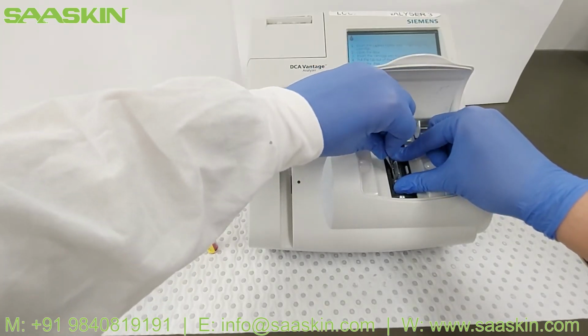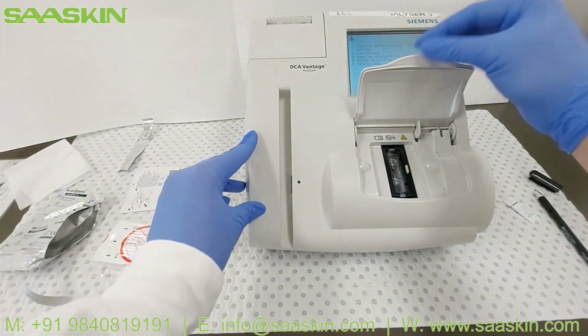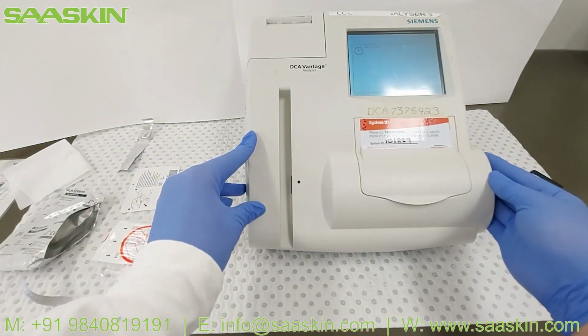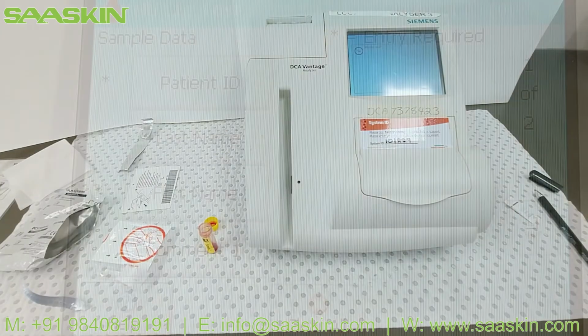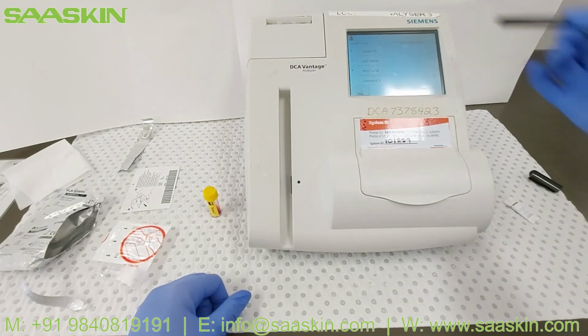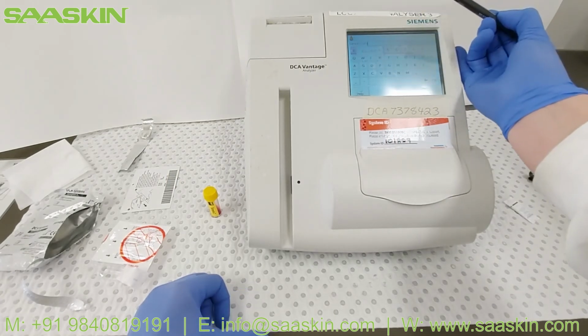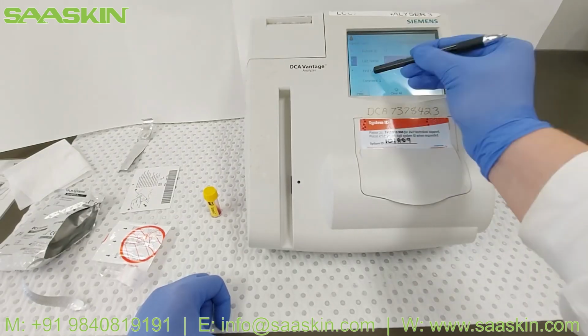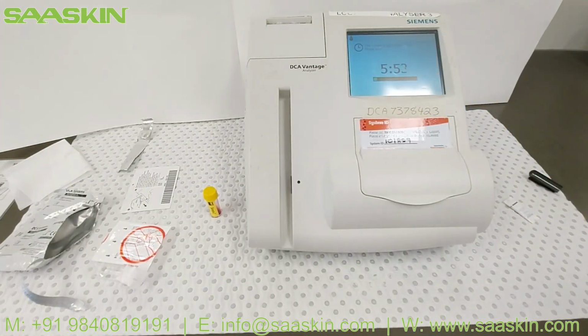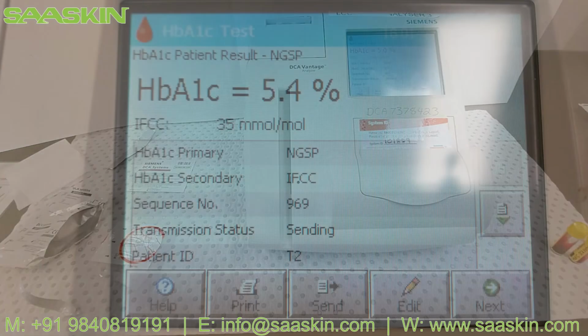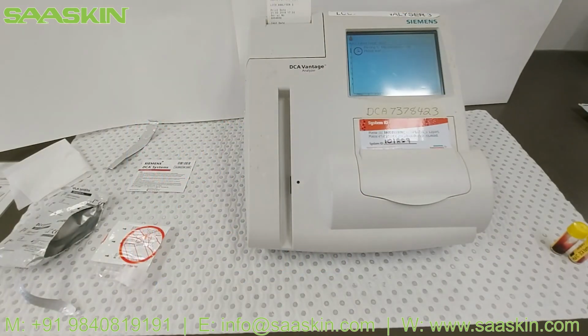Holding the edges of the cartridge firmly, pull the foil tab out of the reagent cartridge and close the reagent cartridge compartment door. The Vantage will now prompt you to add the minimum requirements for patient details, including patient ID, last name, first name, and any comments you may like to include. Once the fields with asterisks have been filled, hit OK to accept and wait for the countdown timer to finish to read the results display. If you require a printed copy of the results, hit the print key. Hit the send key to digitally export the result to the LIS.